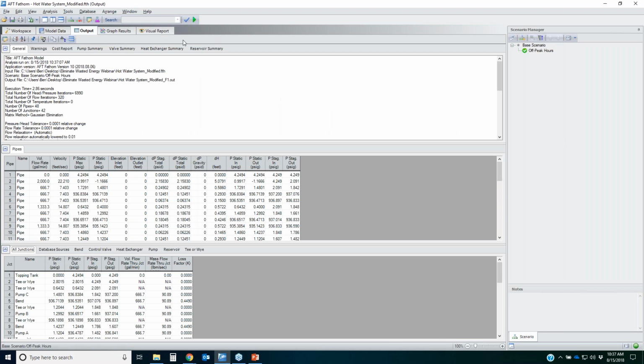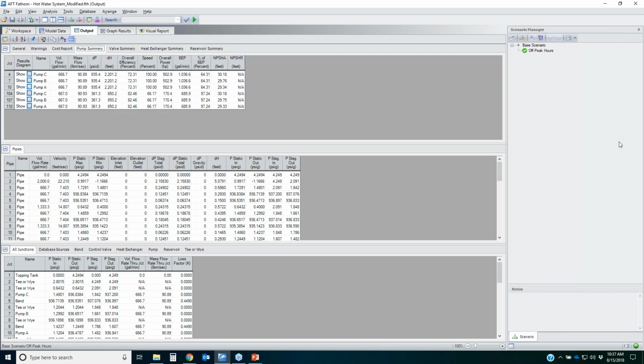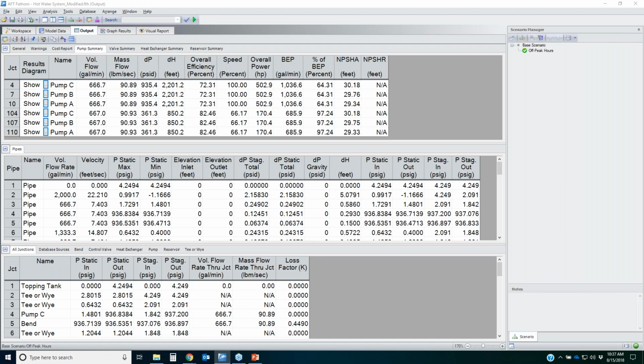When this scenario runs, it calculates all the results like it usually does. If we go to the pump summary tab, we can see where our operation is. Let me click back on my pointer here real quick. And I want to make this text a bit larger. There we go. So let's look at something here. Percent of best efficiency point. When I'm using my flow control valves to control the flow rate, it's operating at 65% of the BEP. That's going to cause some major reliability issues on the pumps. You do not want to do that.